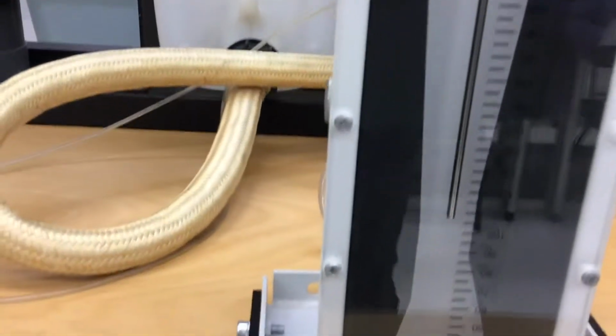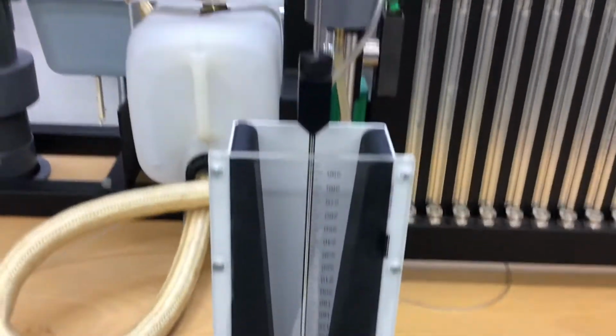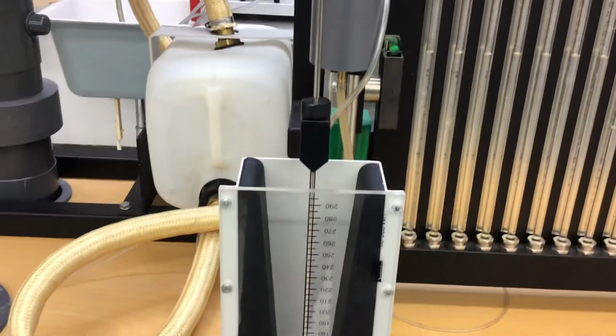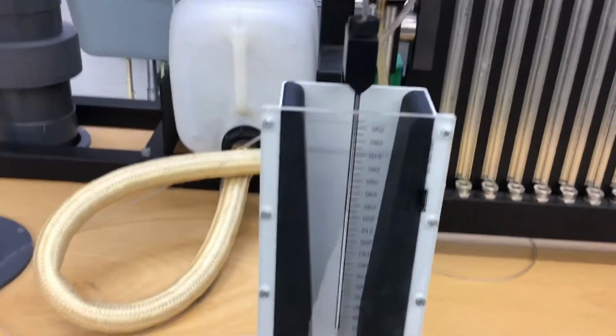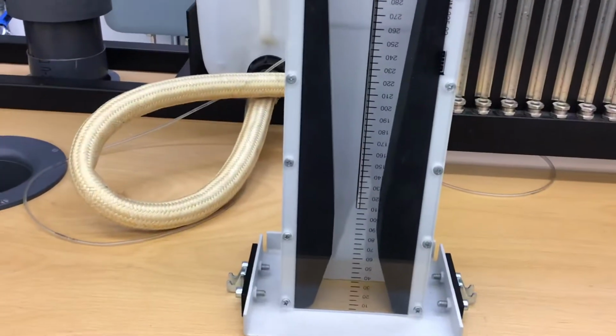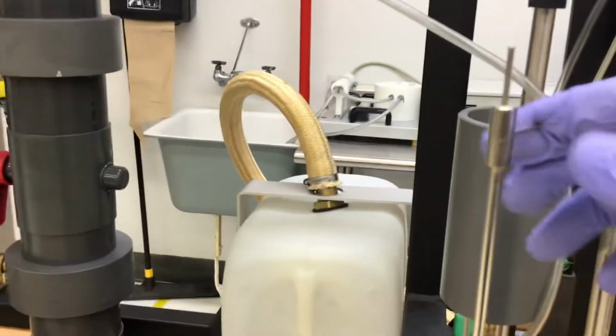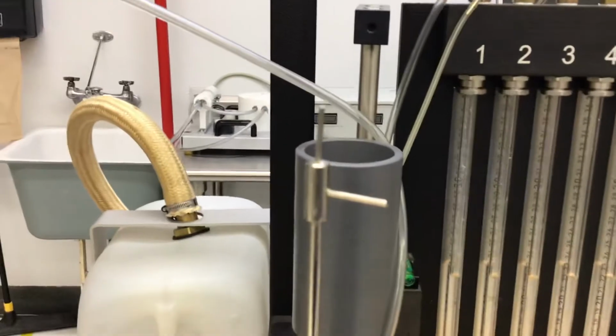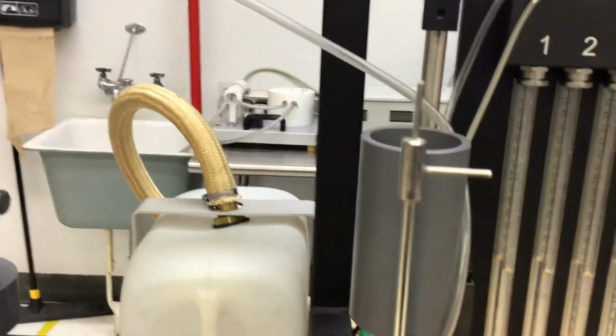So you have two different independent paths inside this tube. One is connected to the front of the tube that measures the total pressure, and the second is connected to the side of the tube, all around the side, and this measures the static pressure.